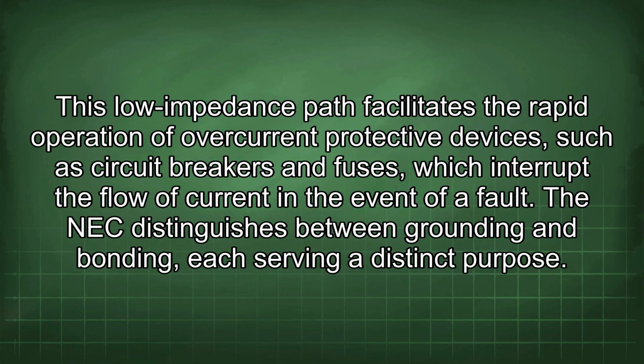This low impedance path facilitates the rapid operation of overcurrent protective devices, such as circuit breakers and fuses, which interrupt the flow of current in the event of a fault. The NEC distinguishes between grounding and bonding, each serving a distinct purpose.